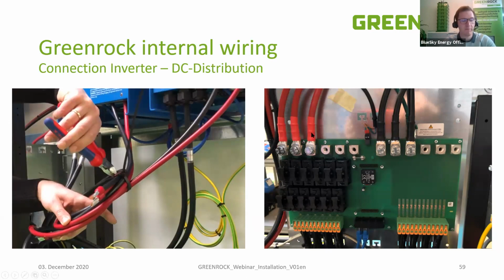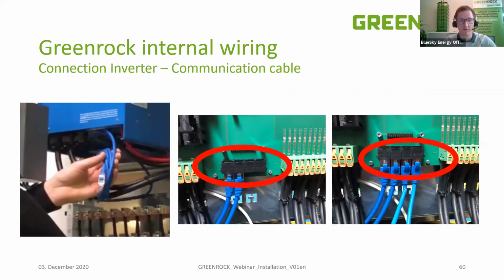Here you have the battery inverter connections, and here the battery connections. There are DC fuses, or 20 amp fuses, on the plus side of each stack. There's also a small 50 volt DC output, fused with 1 amp at 48 volts. On this connection you have 50 volts DC available for accessories, for example for color control if you're using Victron components, or any other accessory that can be powered at this level.